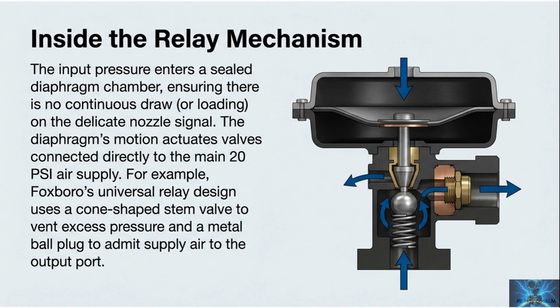Inside the relay mechanism, the input pressure enters a sealed diaphragm chamber, so there is no continuous air draw that would disturb the nozzle signal. Diaphragm motion then controls internal valves tied directly to the main supply air, commonly around 20 pounds per square inch. One valve admits supply air to increase output pressure. Another path vents air to decrease output pressure. This is how a tiny, delicate pressure signal controls a much stronger airflow without being dragged down by the load.